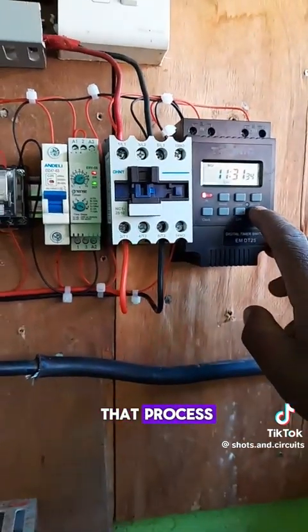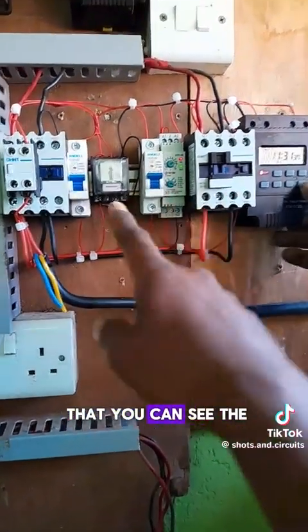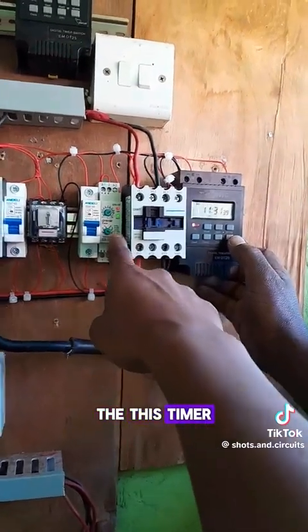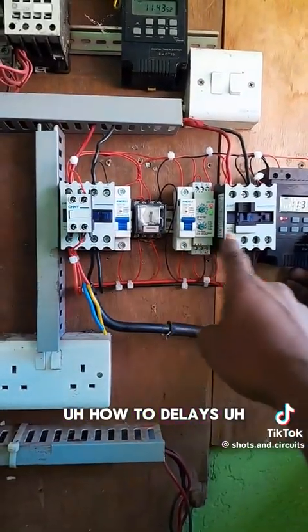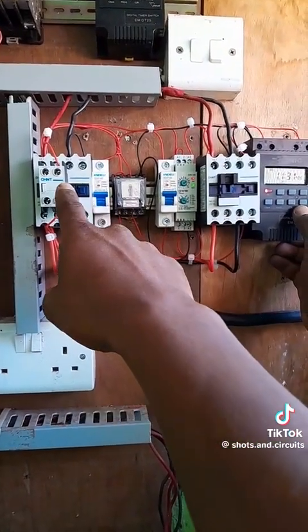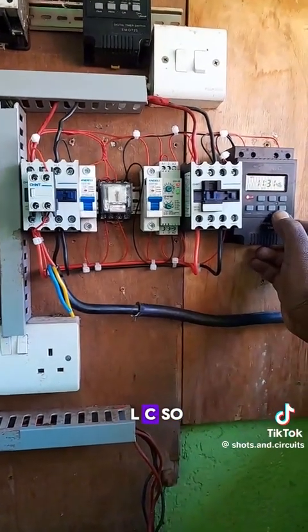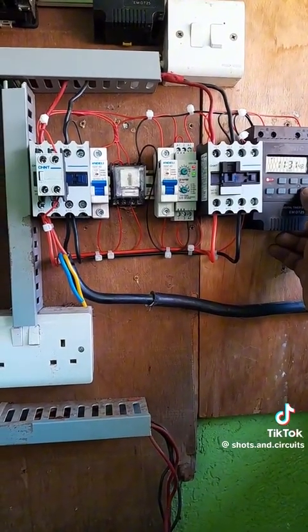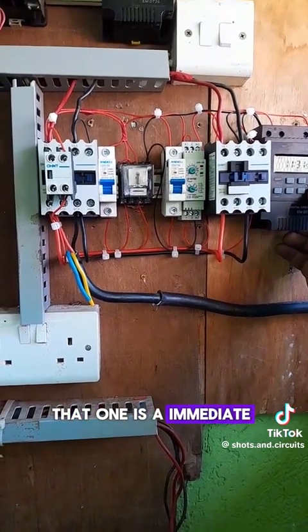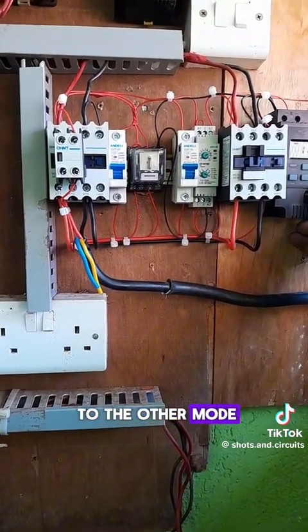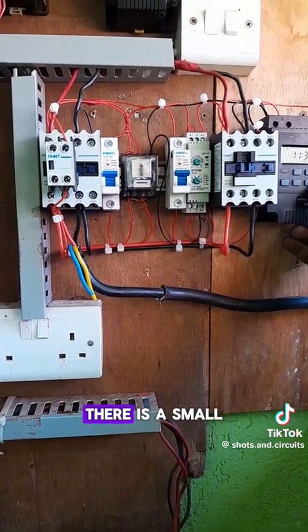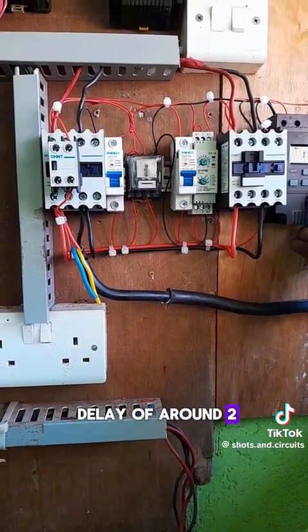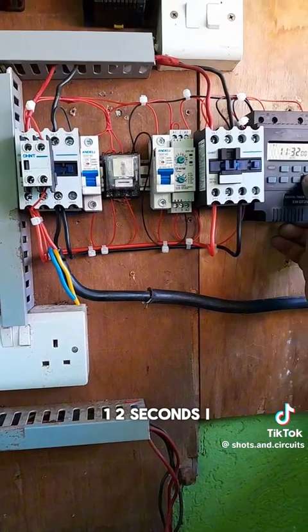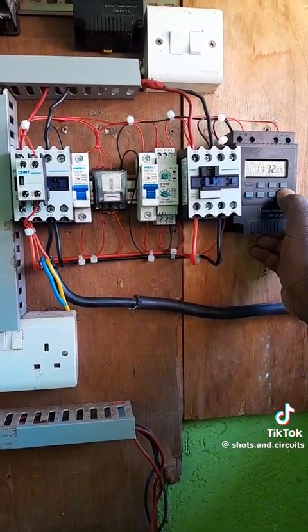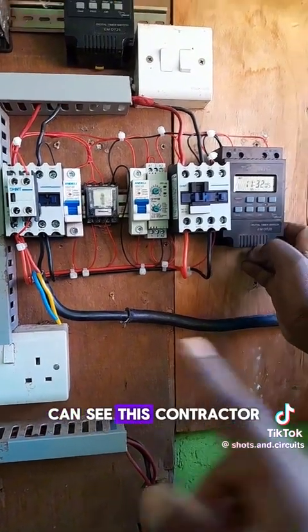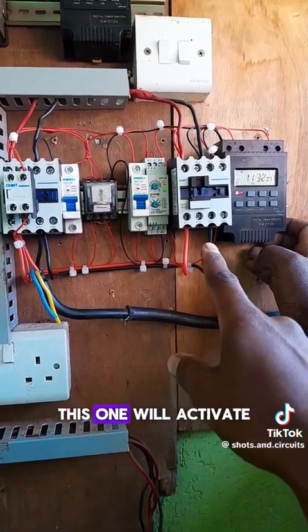So let us repeat that process on a wide angle so that you can see this timer, how it delays the power from solar backup to KPLC. So put it on auto. That one is immediate, but now when switching to the other mode, which is solar backup, there is a small delay of around 1-2 seconds. You can see this contactor will release and then this one will activate.